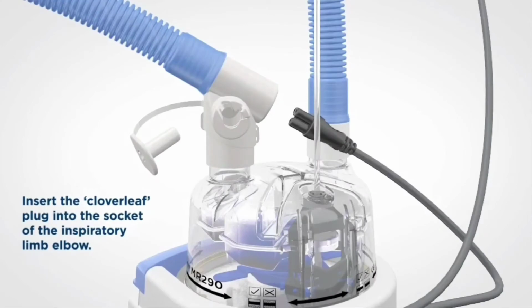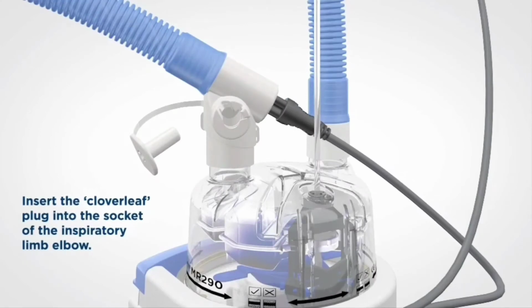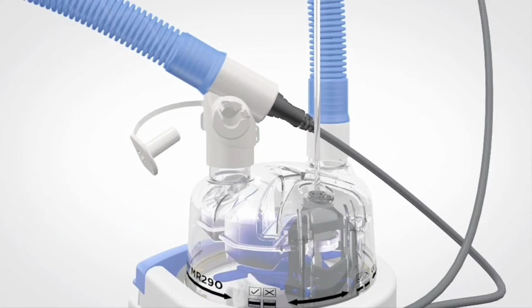Connect the other end of the adapter, shaped like a cloverleaf, to the white socket at the back of the elbow connector on the inspiratory limb. Be careful to line the plug and socket up to avoid damage to the breathing circuit or adapter.